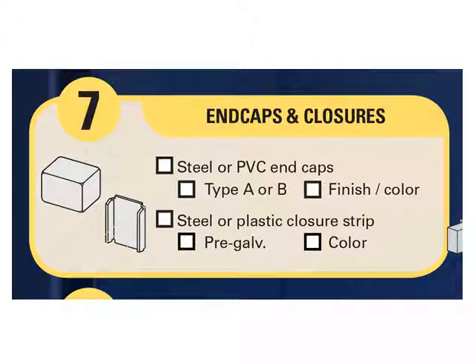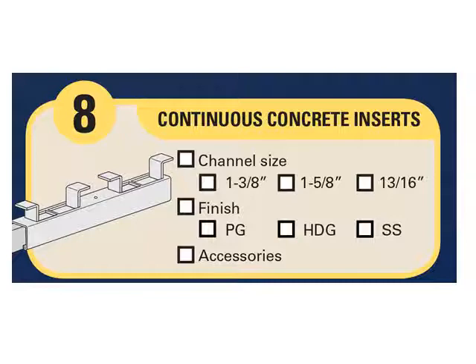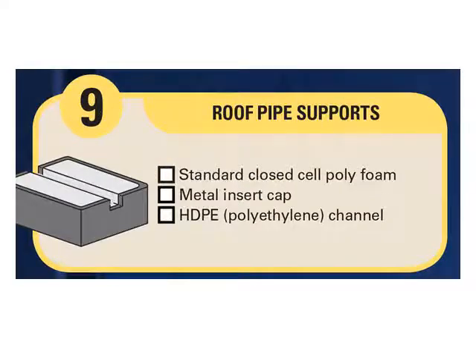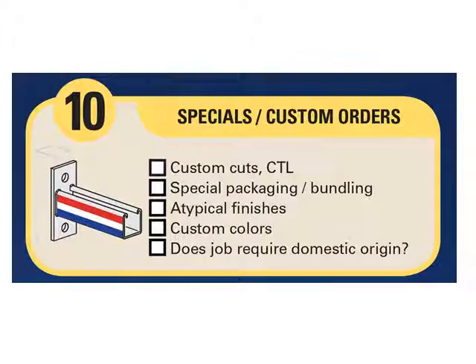Number seven: end caps and closures. End caps provide a finished look to a system while covering sharp edges which may present a cut risk. Number eight: continuous concrete inserts. These are uniquely designed to be cast in concrete, principally in ceilings and walls. Once cast in, the strut functions normally for supporting pipe, conduit, cable tray, and strut systems. Number nine: roof pipe supports. Roof support blocks protect commercial and industrial roof membranes from the weight and construction of rooftop strut systems. Number ten: specials and custom orders. G-Strut will customize to specification including custom cut-to-length, custom colors, special fabrication, and packaging.